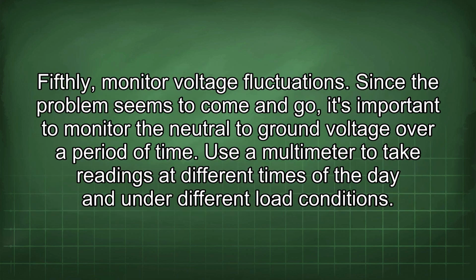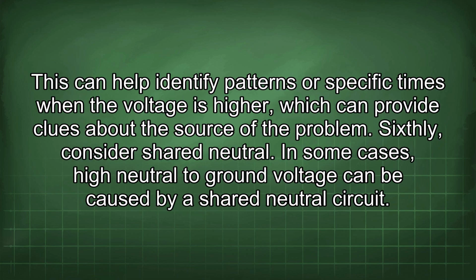Fifthly, monitor voltage fluctuations. Since the problem seems to come and go, it's important to monitor the neutral to ground voltage over a period of time. Use a multimeter to take readings at different times of the day and under different load conditions. This can help identify patterns or specific times when the voltage is higher, which can provide clues about the source of the problem.